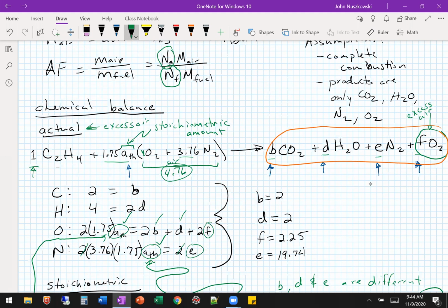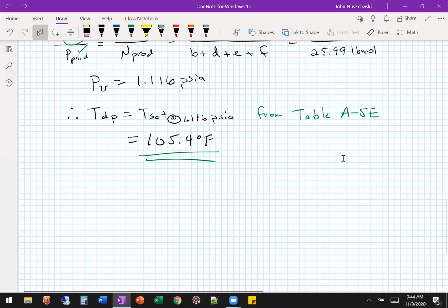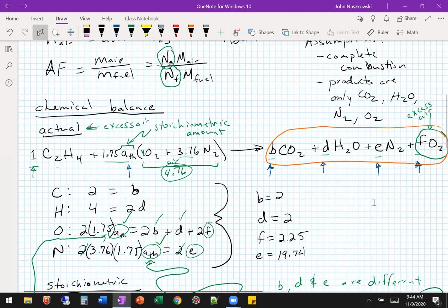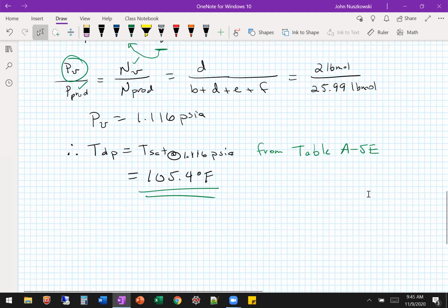So if you're removing water, you're going to change the mole fraction that you're measuring. So in exhaust analyzing systems of exhaust products, you've got to measure with the temperature above that. The other method that they do is dropping out all the water on purpose before measuring, because then the water's not there, so you can calculate and correct for that. But you have to drop everything off of the water.